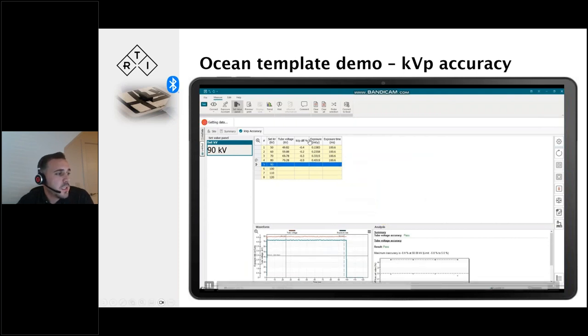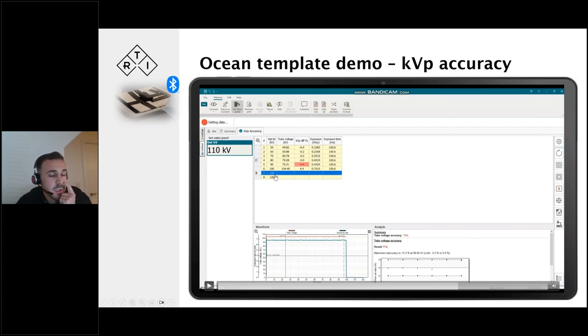Now we've got a hint popped up, we can click OK, carry on with our template. And you'll see all this analysis that you typically do in Excel is already done for you. In this case, I've shown some mock data for what happens when it's outside our tolerance. As we're going through this template, we have a set value, so what you set on the X-ray console, we have the actual measured value, and then we have our custom analysis, which shows the difference in percentage between what it's supposed to be and what's actually measured. Here we have automated analysis, where you can put your criteria, such as plus minus 5%.